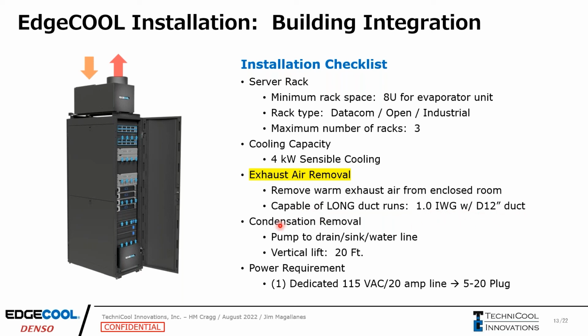Condensation removal: we're pumping to a drain or sink or water line somewhere. We have 20 feet of vertical lift on this pump, meaning it can go up 20 feet, and then horizontally for longer runs to a break room or a bathroom somewhere nearby. And then the power requirement: we're operating again on a 115 volt, 20 amp circuit with a 5-20 plug.